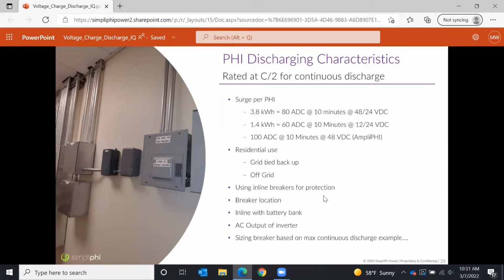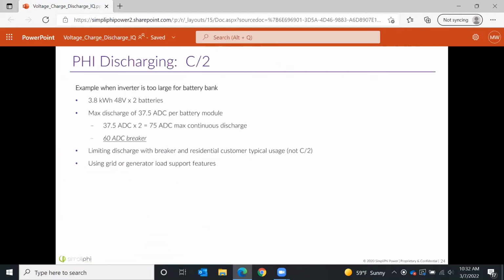One thing that a lot of installers tend to do, in the past at least, we've seen people undersize systems and then use overcurrent protection to try to keep the batteries from discharging too quickly. Now, I would not recommend this. I always recommend using overcurrent protection, but I would do that in addition to sizing the system properly. And here's why. Let's do an example.